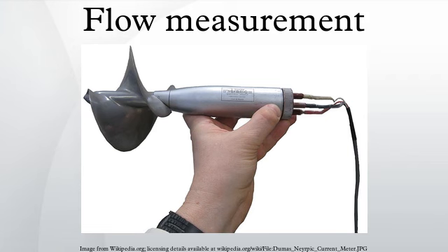The flow must be kept steady during the traverse of the current meters. Methods for testing hydroelectric turbines are given in IEC Standard 41. Such flow measurements are often commercially important when testing the efficiency of large turbines.